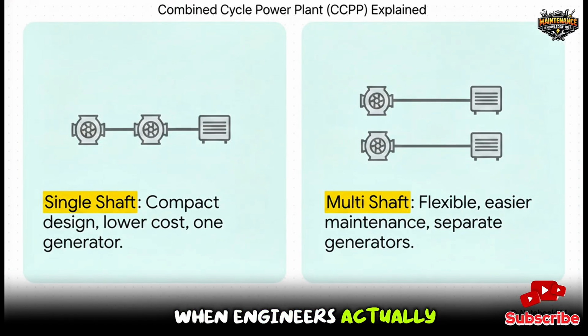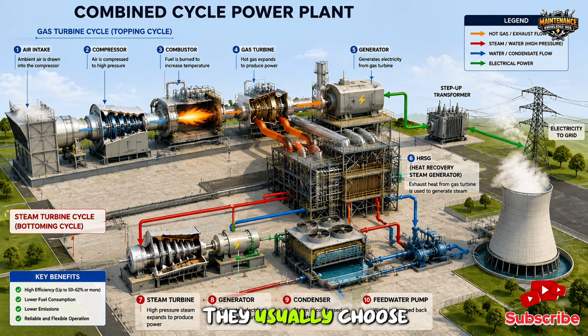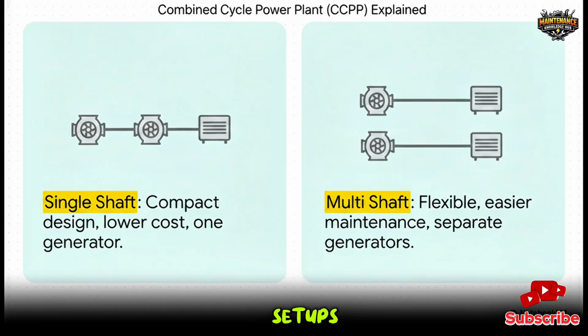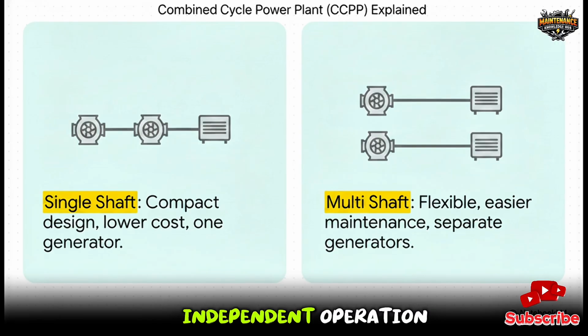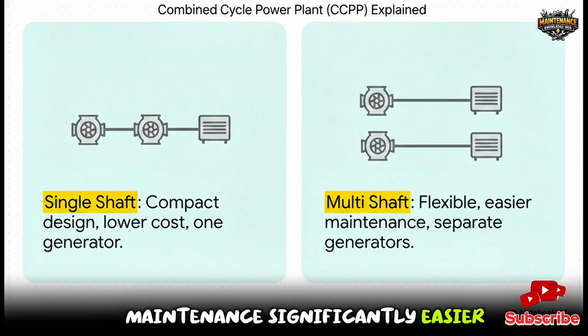Now, when engineers actually build these mechanical beasts, they usually choose between two main setups. The first is a single shaft design. This is where the gas turbine, the steam turbine, and one single generator all share the exact same shaft. It's super compact and means lower installation costs. The alternative is a multi-shaft setup. Here you actually have separate generators for the gas and steam turbines. This allows for independent operation, giving the plant way higher flexibility to respond to grid demands. Plus, it makes maintenance significantly easier.